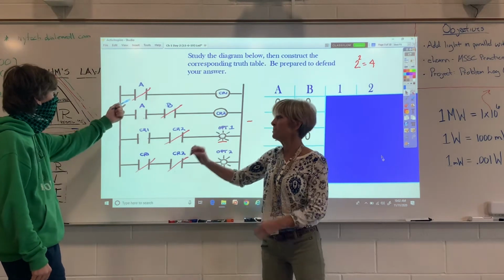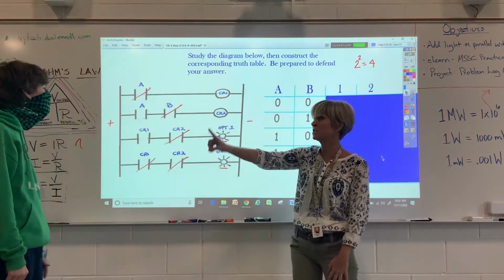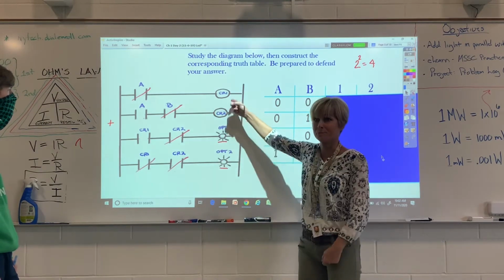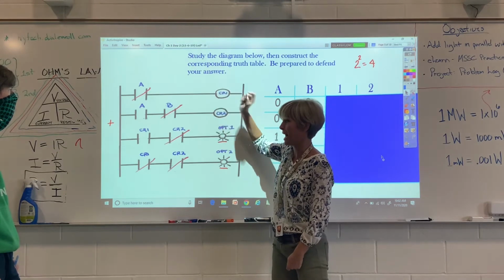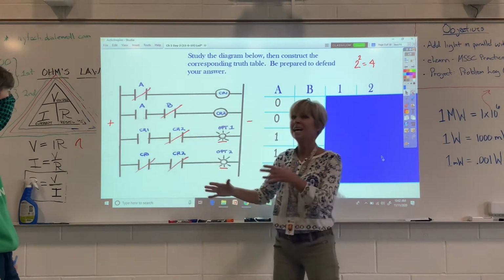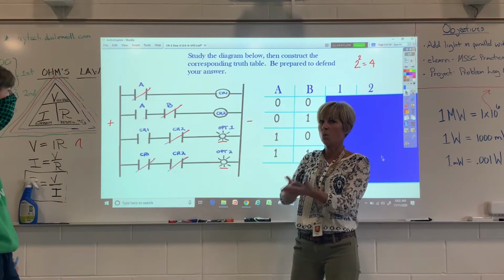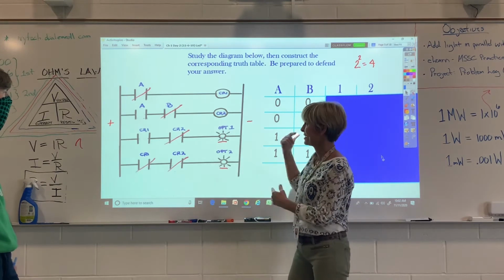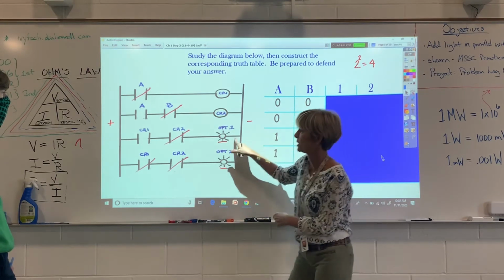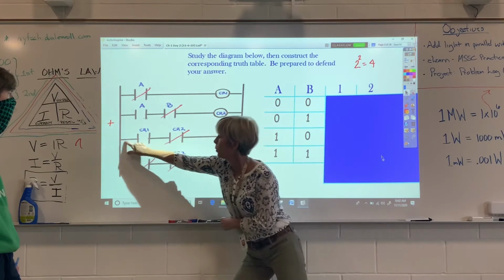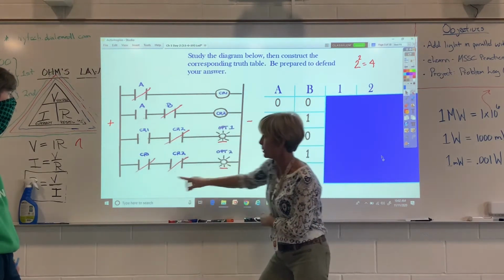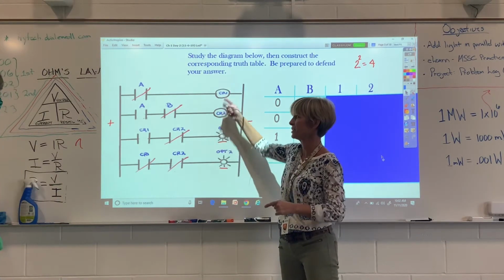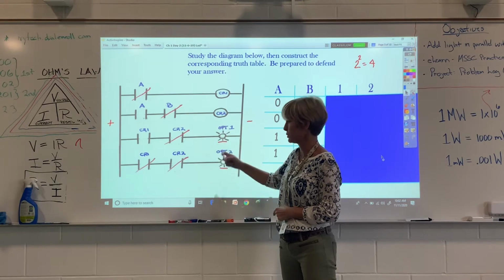So Ben, I'm really glad you said that because this is the exact same thing I used to do all the time. I'd say to Kriegel, I don't understand. It seems to me that right now, this is getting power, so why isn't that closed? And it's because they can wire it any way they want, okay? So what you have to do literally, and this is why I wanted to talk about this, is because this makes it so much easier at the beginning to go, literally, here's my output. Can the current get there or not? Here's my output. Can the current get there or not? The way it's wired at the moment, however these settings are, this isn't getting any juice, this is.